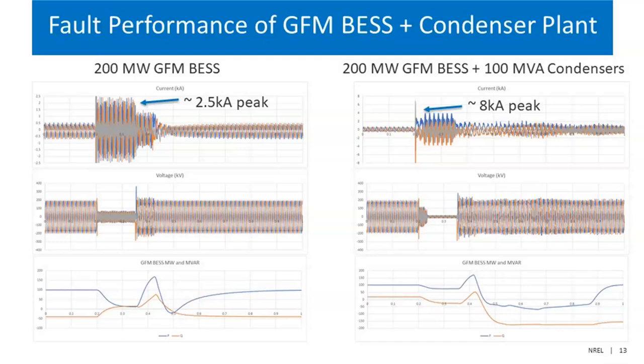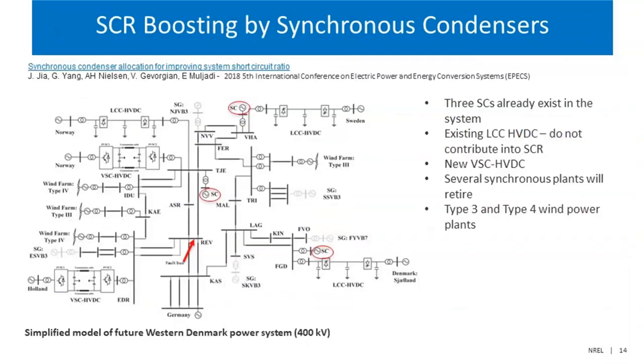So in terms of short-circuit ratio boosting, we didn't do that particular study for Puerto Rico, but this is an example of a study we participated in with the DTU in Denmark on the role of synchronous condensers and their optimal locations in the Western Denmark power system grid. This is a model of their 400 kilovolt transmission system in Western Denmark, which is also going through rapid transition, with a lot of HVDC lines coming in, existing and new. Generators will be retired and a lot of wind is coming up, so the short-circuit ratio is degrading.